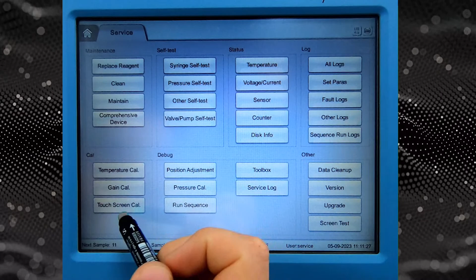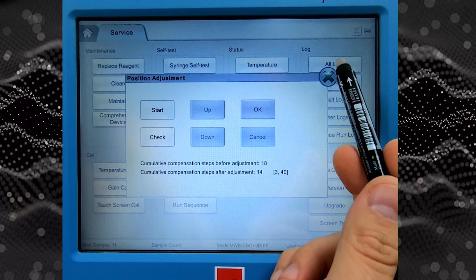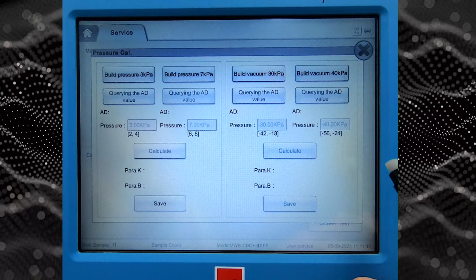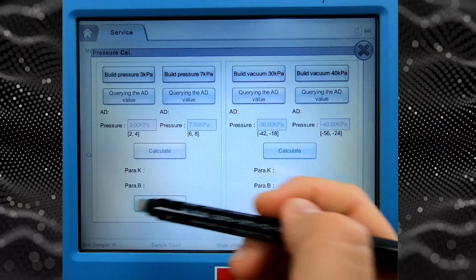Touchscreen calibration. So this is a menu which allows you to calibrate the touch panel. Position adjustment. So this is the up and down position of the rinsing head. Pressure calibration. Please do not change anything here. I don't even know how to use it, actually. No one explained this to us, so they only said do not use it, do not change anything.